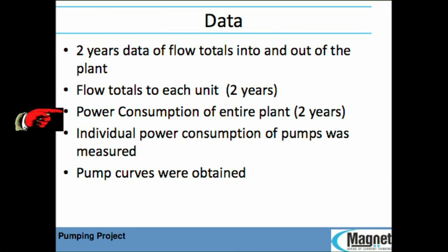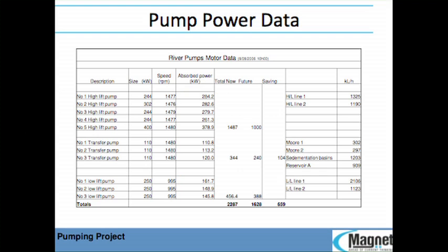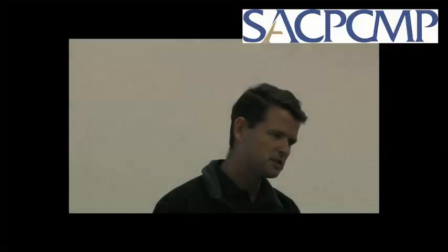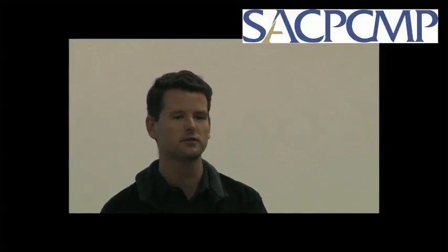We started looking at the power consumption of the entire plant. How does it change? Then you start getting more detailed individual power consumption of each of the pumps. Get all the pump curves, dig those out. Did a mass balance across the whole plant for different scenarios. When the water's dirty, how much water can you put through each of the processes? When the river water is clean, and then effectively it boils down to in summer, how much can you process in winter, and what's the average?